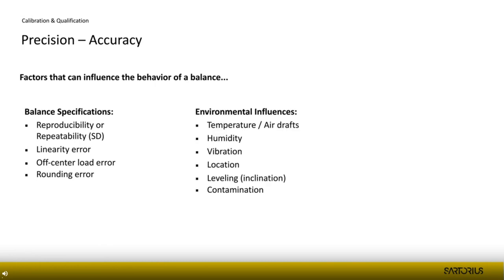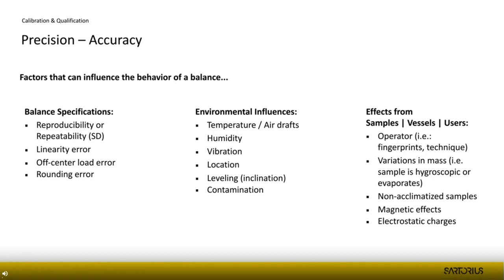We also have environmental influences on the measurement and balance behavior, such as temperature, humidity, location, and leveling — everything affecting instrument performance. And there are factors from samples, vessels, and users, like fingerprints, hygroscopic samples, or magnetic effects. These are the factors that affect sample behavior while weighing.